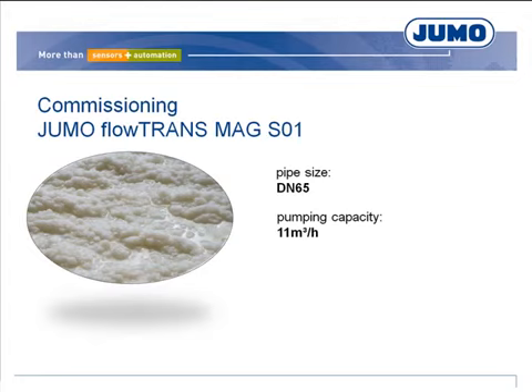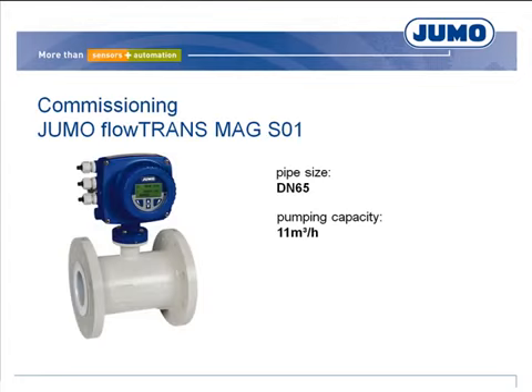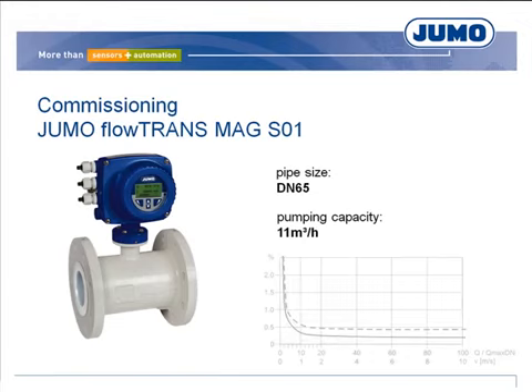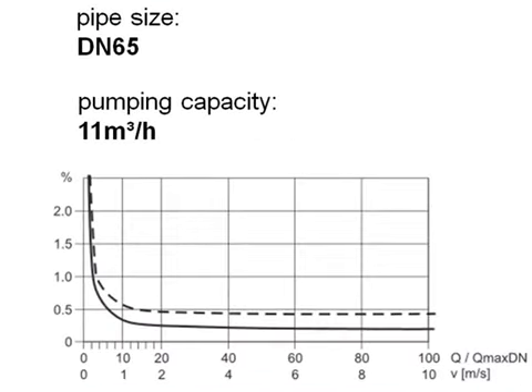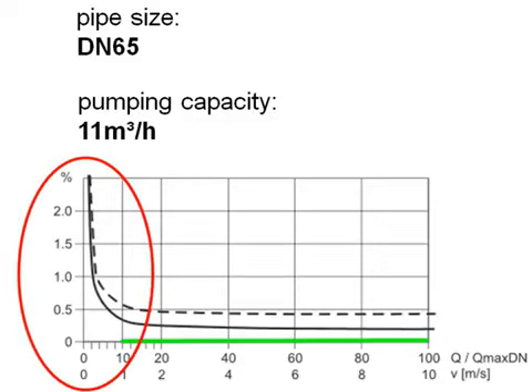Due to the viscous medium and the limited space, the decision is made for the magnetically inductive flow meter JUMO flowTRANS MAG S01 with standard PTFE lining. For optimum results, the flow rate in the flowTRANS MAG should be between 1 and 10 meters per second. If it is significantly less, the existing pipeline system has not been planned economically and the pipelines are too large in relation to the flow rate.